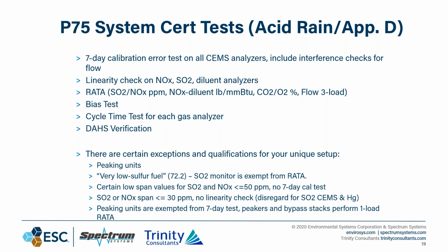And I have seen air permits not mention Part 60, even though you do have a CO analyzer at your site. And the permit may state you will follow all conditions of Part 75. You might have to work with your agency on that a bit to see if you're going to fully harmonize Part 60 and 75 and treat the CO analyzer as you would under Part 75. There are sites that do complete separate Part 60, Part 75 certification and recert tests.